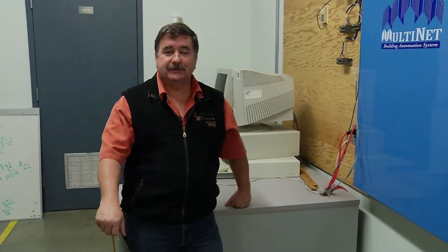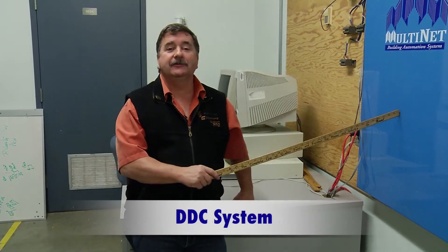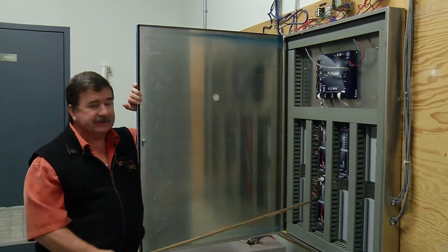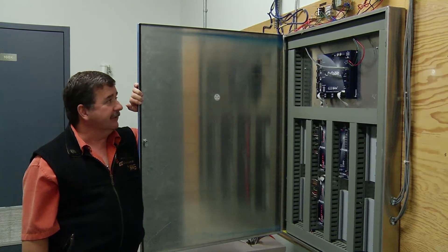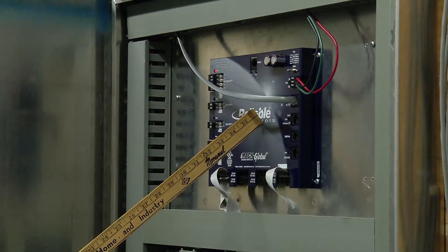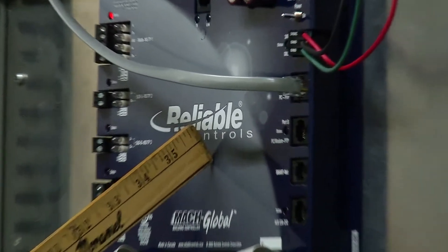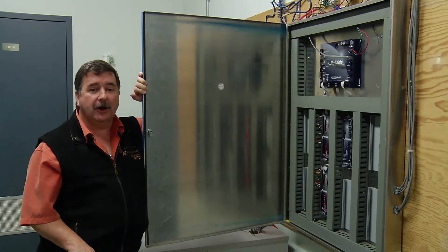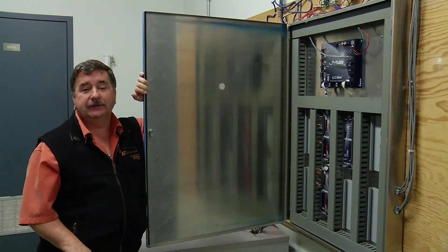Building systems are usually controlled by a DDC system these days. Here we have a training example of one of those DDC systems. Inside you've got a bunch of relays and contacts that control the operation of your rooftop air conditioners. We have a brain here with communication capability so that we can set up programs to do load shedding, time tabling, and to command spaces on and off so that we're not heating or cooling when there is no need.